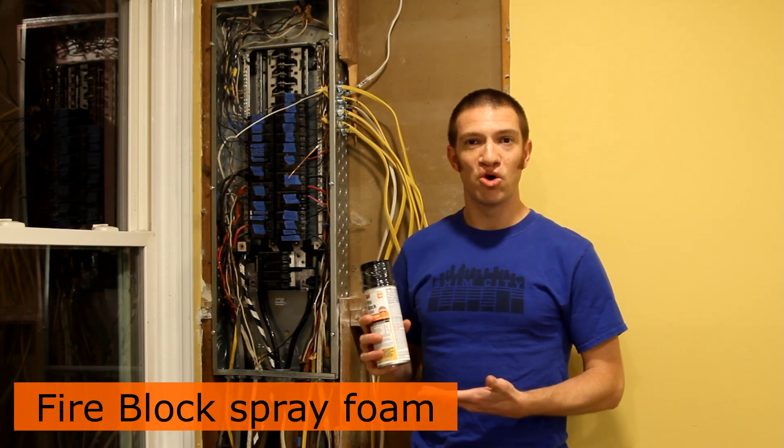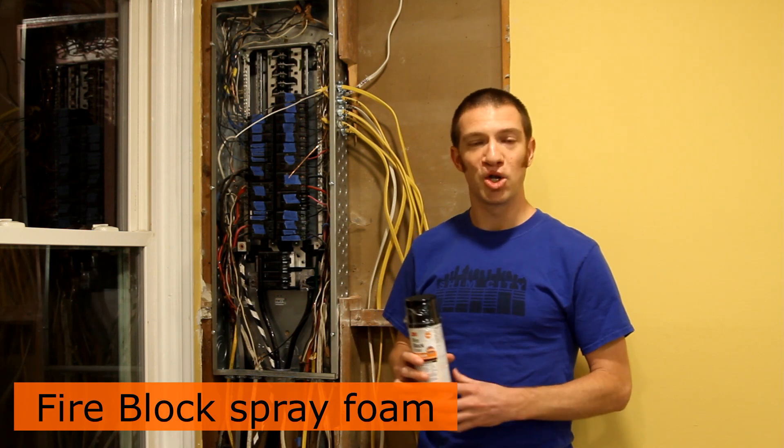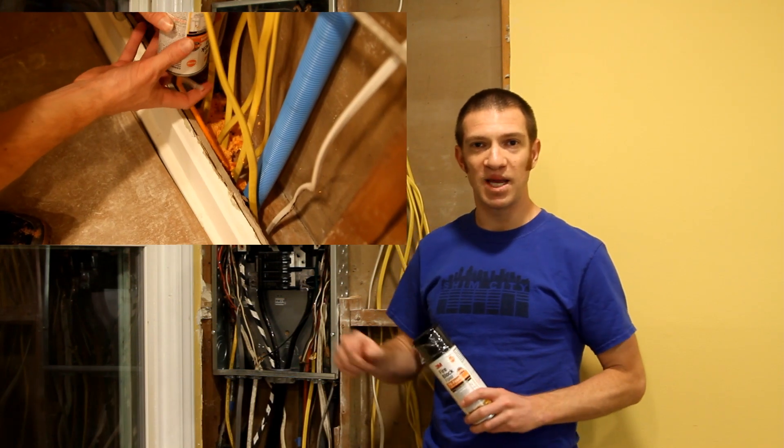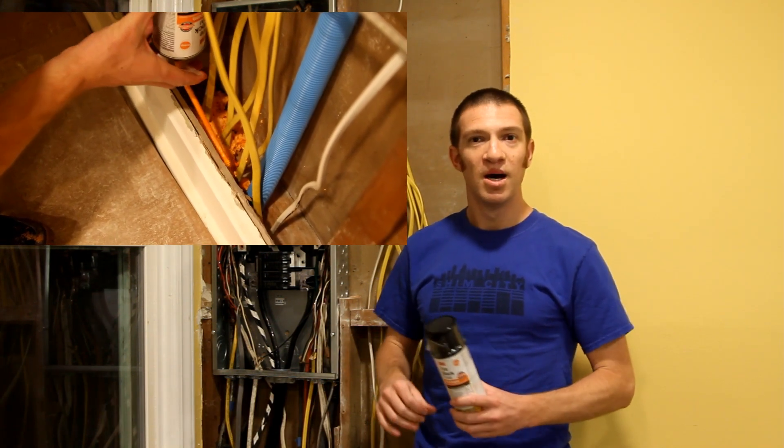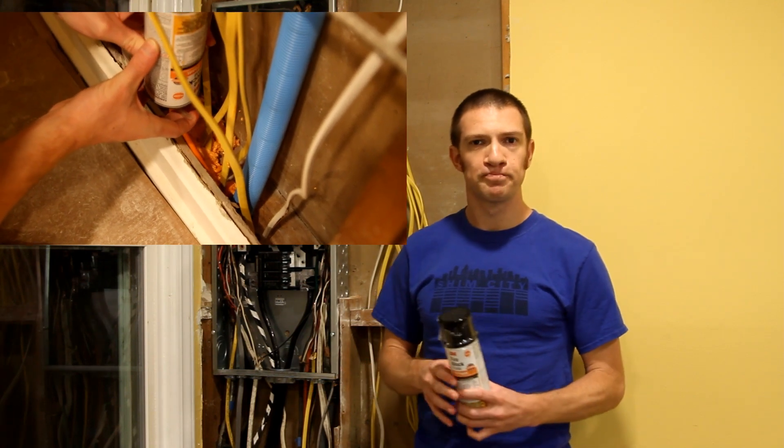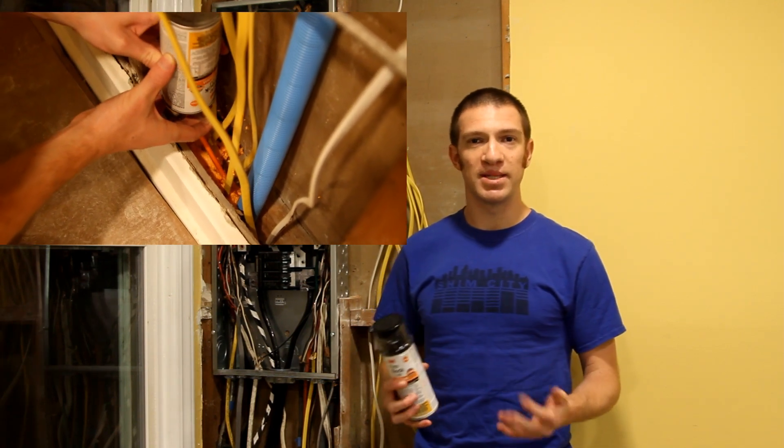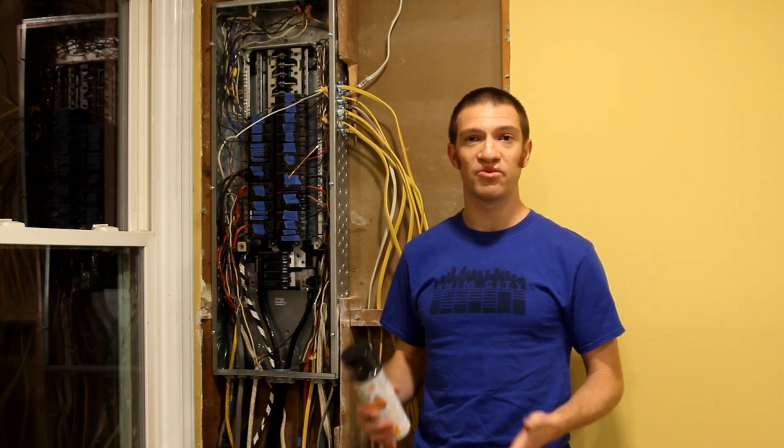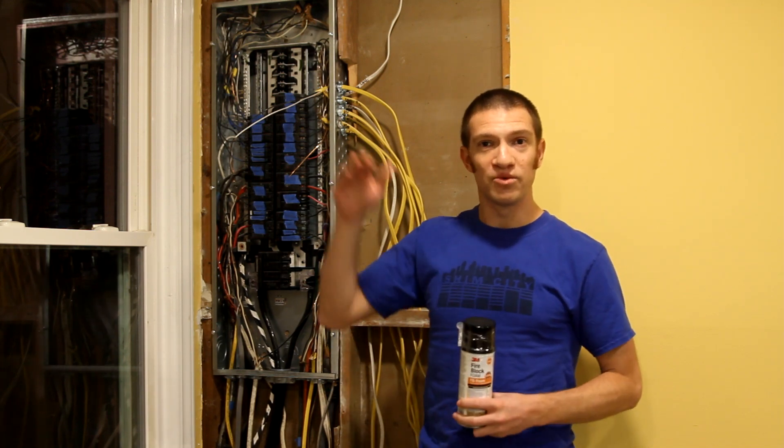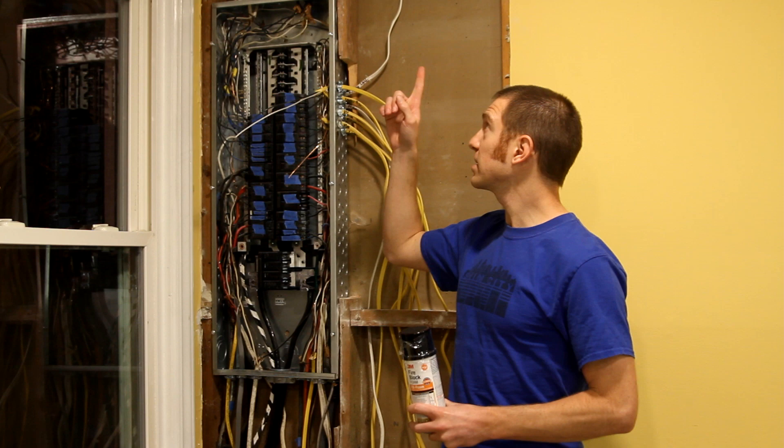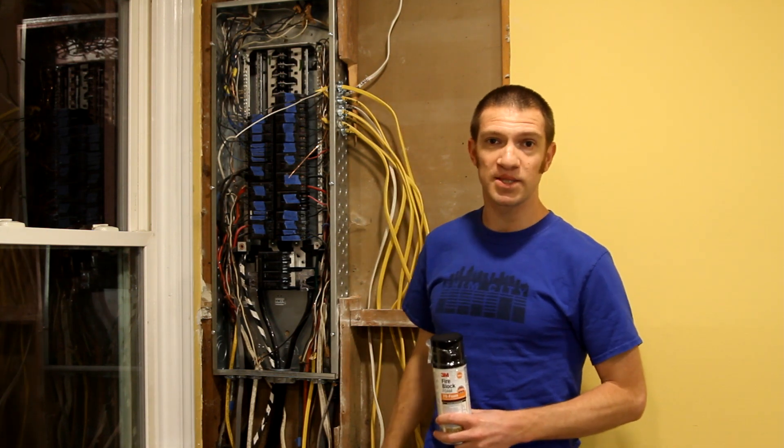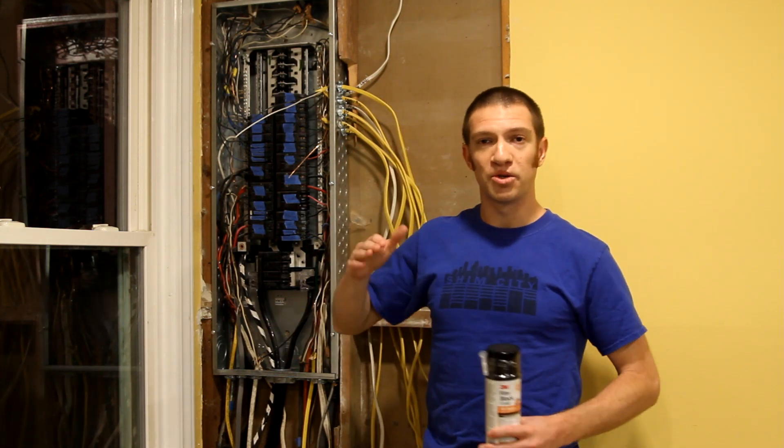I use something very simple called fire block spray foam. This is an orange foam, it comes in a couple different brands, and all you have to do is spray a little bit of this into every penetration that you just made and any cracks you see. This is code required to basically prevent the flow of fire or prevent the flow of oxygen to a fire on various levels. So you'll hit your attic holes, you'll hit your crawl space holes, and then any other floor penetrations.